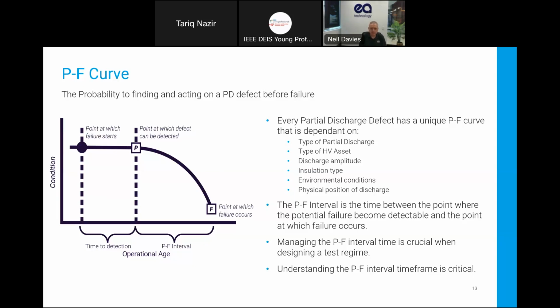The environmental conditions, if we're in a damp, humid environment, surface tracking inside of metal clad switchgear will accelerate away much more quickly. And the physical position of the discharge, is it discharge into solid insulation, metal to metal type discharge. All of these things will mean that the P-F interval is not easily defined. So managing that is difficult, you can't do it on a one size fits all basis.